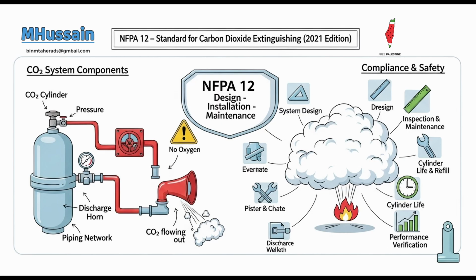Why so much? This 40% increase isn't just a buffer, it's a stark reminder of the physics at play. A significant portion of the initial CO2 blast from a high-pressure cylinder effectively vaporizes and becomes gas almost immediately as pressure drops before reaching the target. A lot flashes to gas right away and doesn't make it as liquid. Exactly. This underscores the engineering challenge of delivering the critical liquid agent efficiently in these systems. Furthermore, extra CO2 is needed to compensate for any liquid that vaporizes in cooling the piping. Gas loss cooling the pipes, which can be significant in long runs, especially in colder environments.